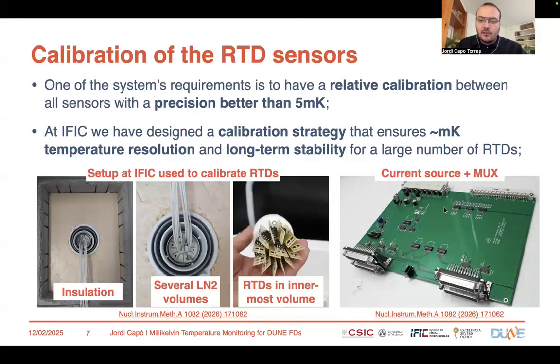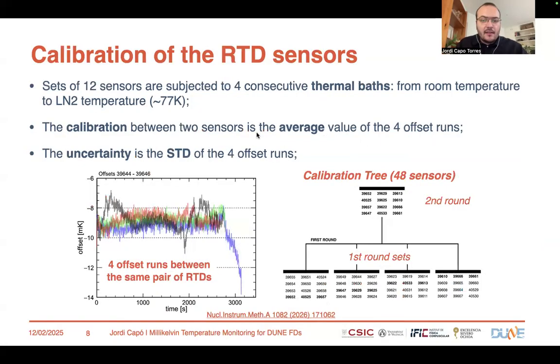We use this current source described in this paper, and all of this setup is also described in the paper, so you can have a look at it if you are interested. So here are some more insights of how this looks. We divide our sensors in sets of 12 sensors, and we subject them to 4 consecutive thermal baths from room temperature to liquid nitrogen temperature. And you can see here how the readout of the temperature measurements looks when the sensors are immersed during these 4 consecutive baths. We evaluate the calibration constant as the average of the means of each of these 4 consecutive runs, and the uncertainty we associate to the standard deviation of these 4 means.